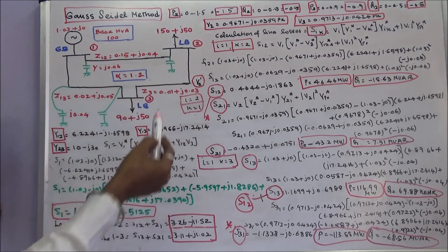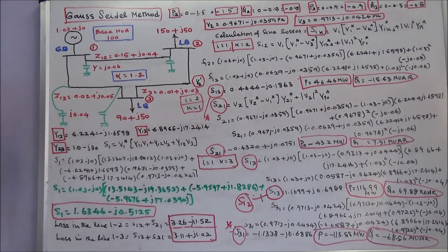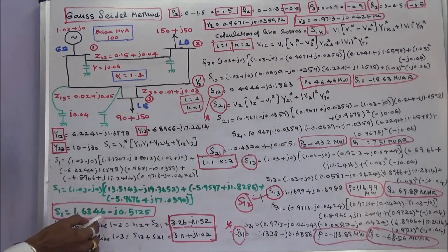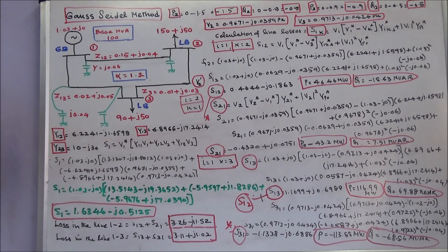Similarly we can calculate the line losses for lines 2-3 and 3-2 to get the total line loss in line 2-3. Next, the slack bus power S1 = V1* × (Y11×V1 + Y12×V2 + Y13×V3). Substituting all values, the slack bus power is 1.6346 minus j0.5125 per unit. We can verify this by adding S12 + S13 to get the same answer. This is how we calculate line losses and slack bus power.